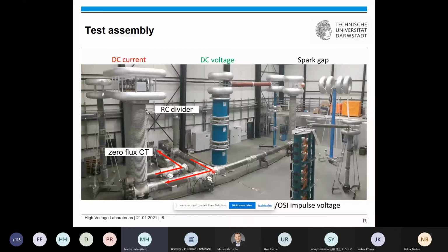We also have an impulse voltage generator to investigate the overvoltage behavior of the assembly. For that, we are not using conventional lightning and switching impulse. We are using oscillating impulses. I will explain this later on, to put the overvoltages to the DC voltage. So this is a superimposed voltage test.